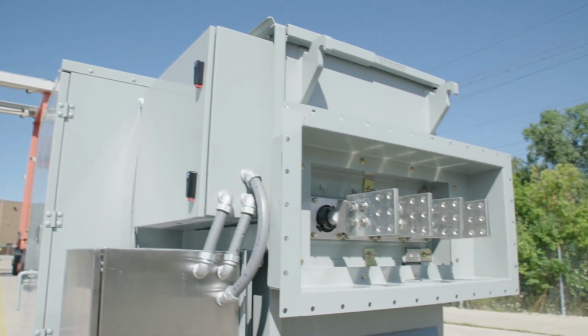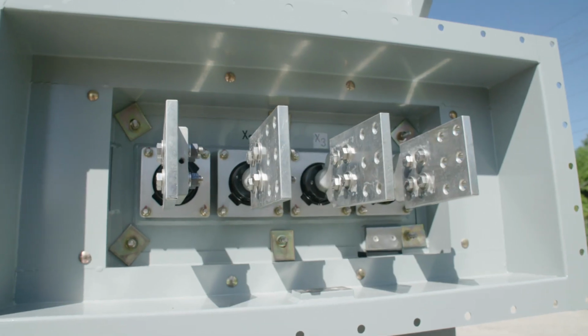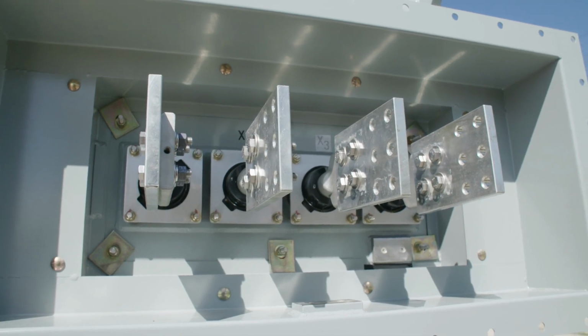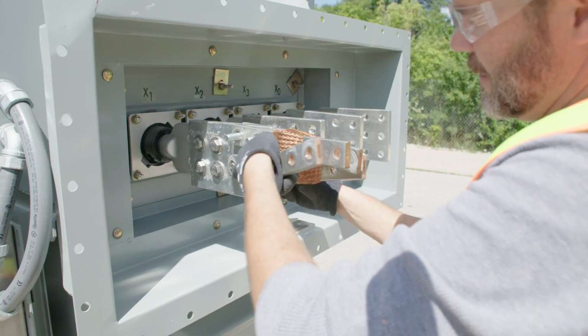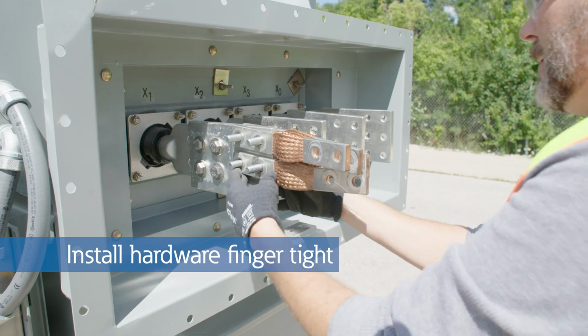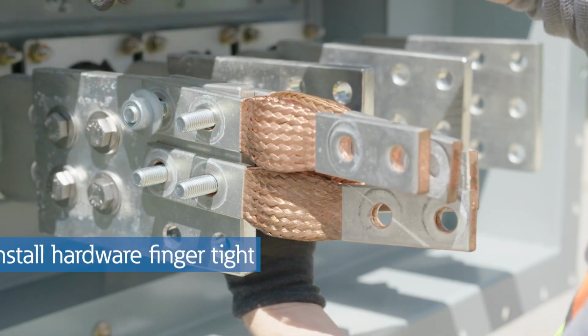The transformer low-voltage flange bushing extensions are shown ready to receive the flexible connectors previously removed from the switchboard. Install the hardware finger-tight and dress the flex connector alignment to the top holes of the bushings. Tighten each half-inch bolt to 50 foot-pounds with a calibrated torque wrench. Spread the ends of the flex leads apart for each phase and neutral connection to facilitate the final placement of the switchboard. Using a Phillips head screwdriver, remove the plastic thread protector inserts from the grounding pad located at the bottom inside surface of the transformer throat.